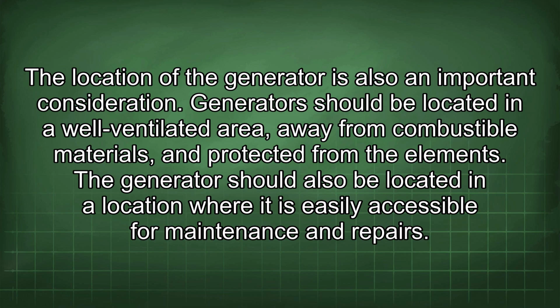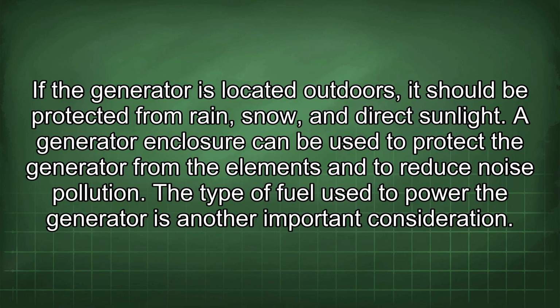The location of the generator is also an important consideration. Generators should be located in a well-ventilated area, away from combustible materials, and protected from the elements. The generator should also be located in a location where it is easily accessible for maintenance and repairs. If the generator is located outdoors, it should be protected from rain, snow, and direct sunlight. A generator enclosure can be used to protect the generator from the elements and to reduce noise pollution.